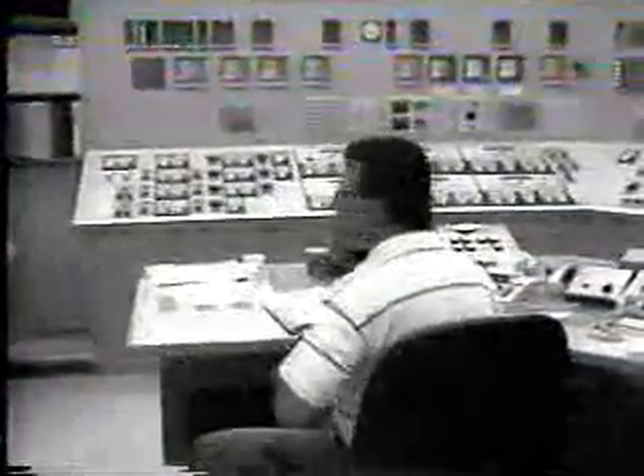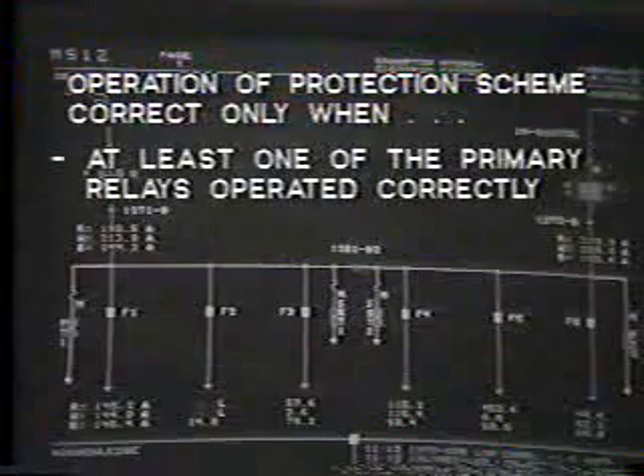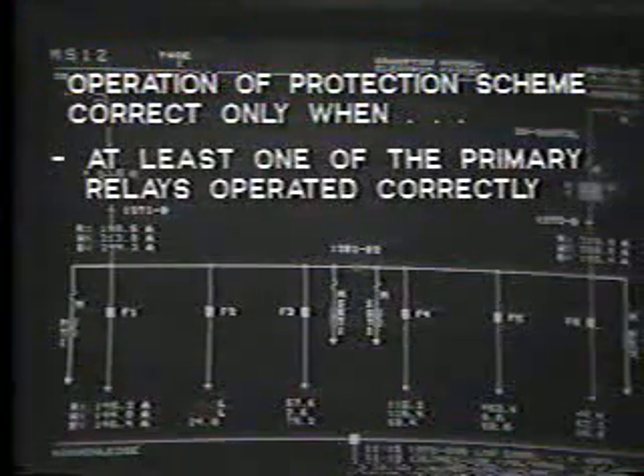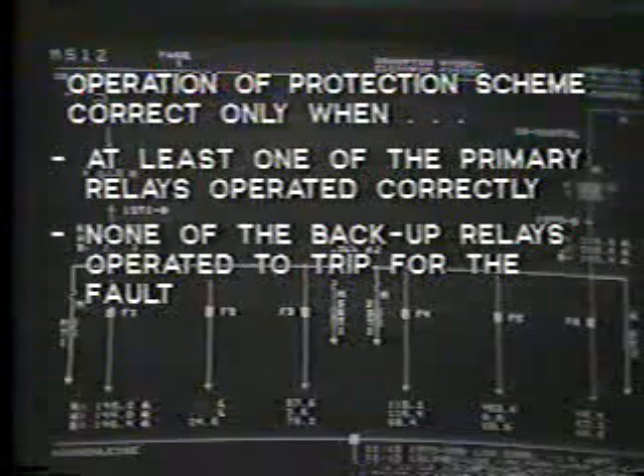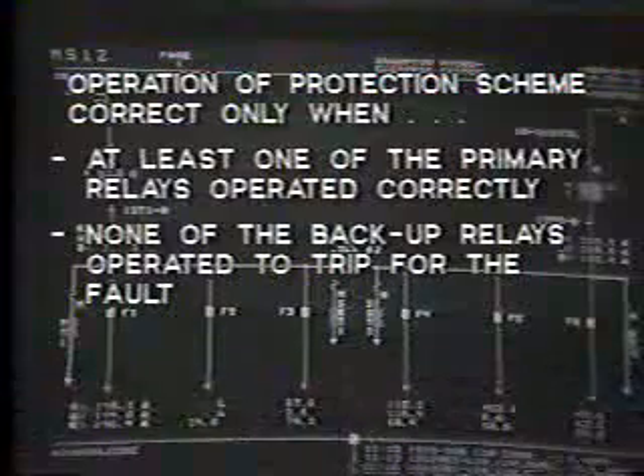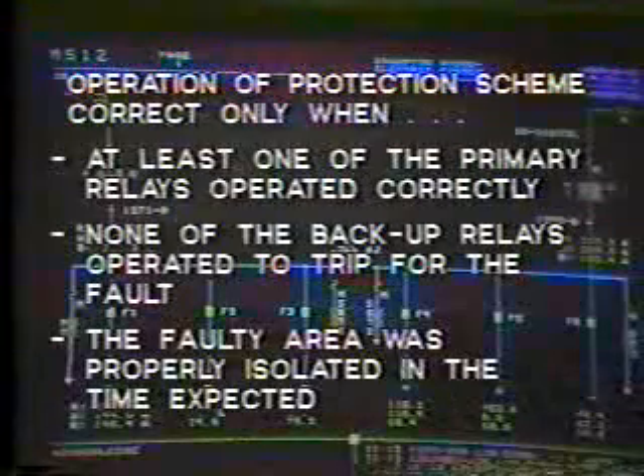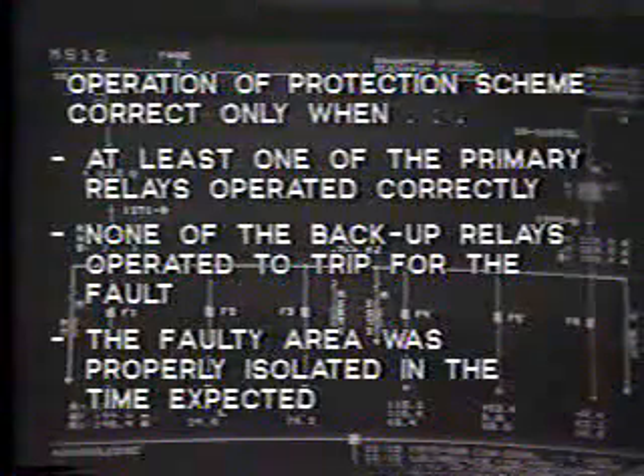In most utility companies, operation of the protection scheme will be classified as correct only when the following conditions have been met. That is, one, at least one of the primary relays operated correctly. Two, none of the backup relays operated to trip for the fault. And three, the faulty area was properly isolated in the time expected. Obviously, knowledge of all conditions on the system at the time of relay operation must be known. This will bring to light, in some cases, incorrect operation of the protection system. This could cause, perhaps, isolation of a no-fault area, or even worse, a failure to isolate the trouble area.